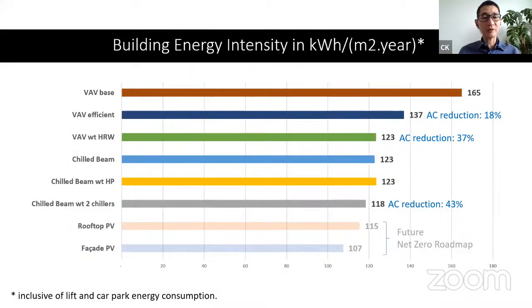So in terms of building energy intensity, we did some modeling very early on in the project. For a VAV base case, according to ASHRAE 90, this building would have consumed about 165 kilowatt hours per meter square per year. If we use a very efficient VAV system, there's an 18% reduction. If we add the heat recovery wheel to it, it has another major reduction because it pre-cools and pre-dries the fresh air coming into the building, because remember, there's a very high fresh air requirement.